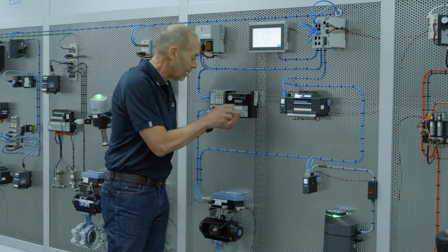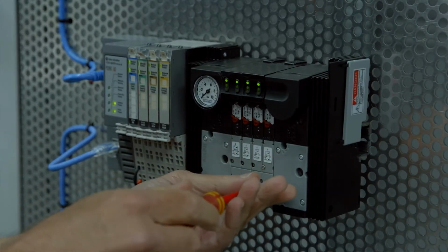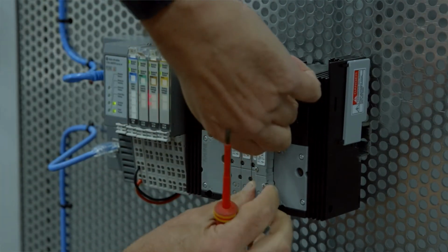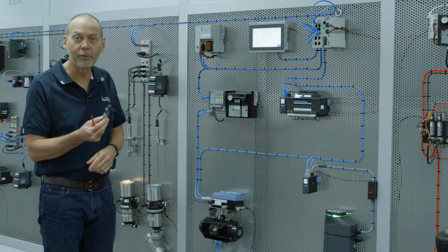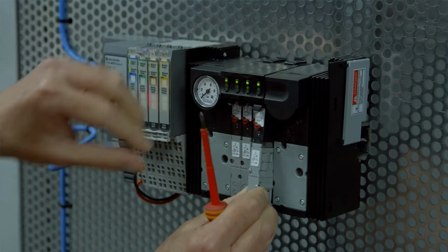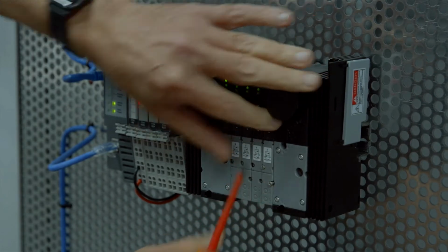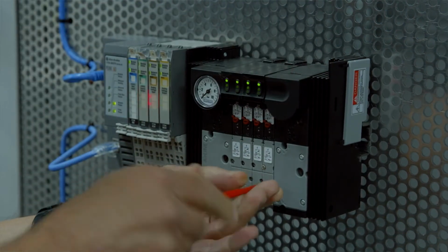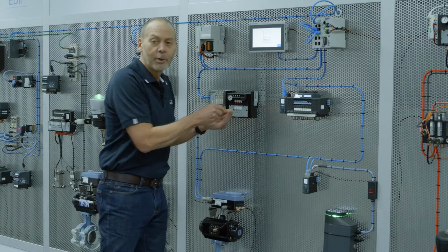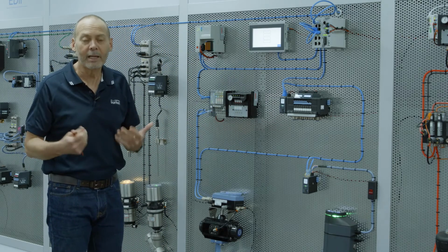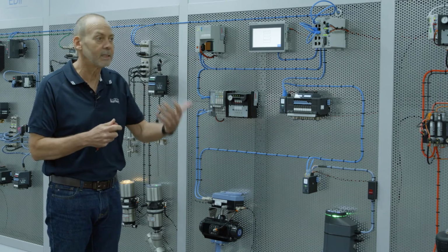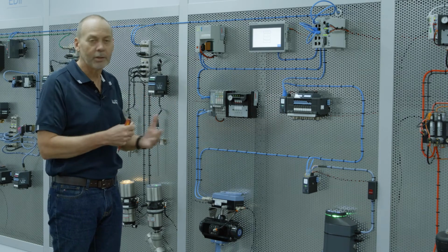We have the option of having a full hot swap capability to swap out valves under full operational, so full air and full electrical connection. And of course you can replace the valve and get back up and running in a very quick period of time. We do this as Bürkert is designed to run in a process automation industry. And in process automation you have things like fermenters and distillation, etc. You can't turn those processes off.